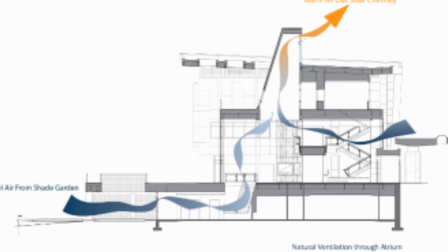This issue is of greater importance in new buildings with more airtight envelopes. To avoid the hazard, many modern combustion appliances utilize direct venting, which draws combustion air directly from outdoors, instead of from the indoor environment. Categories of ventilation.